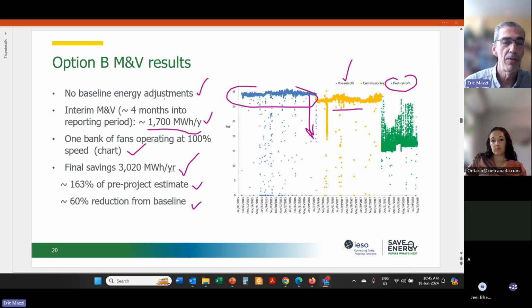But that's the other practicality of real world projects. Often in a retrofit like this, maybe the CO2 sensors were put in as part of the VFD project, but you had no baseline data for CO2 levels, and CO2 levels were your measure of occupancy. Well, you can't build a baseline model of energy consumption versus CO2 level to carry out an adjustment if you have no baseline CO2 data. Does that help answer the question? I hope so. Yeah, really good. Thank you.